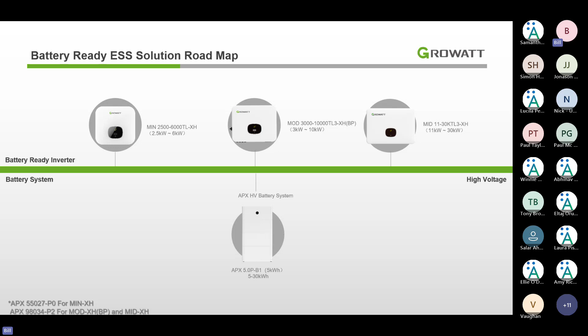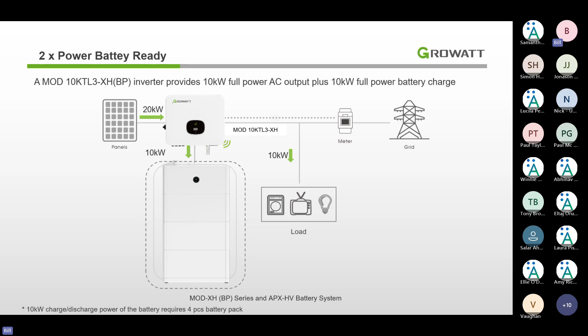Here's an example for the MOD system. So imagine this product goes up to 10 kilowatt. This system will allow like 20 kilowatt from your panels, and it will separate like 10 kilowatt to charge your batteries, and the other 10 kilowatt will feed your loads. Remember here, since this battery is 0.5 C, that means a 5 kilowatt hour battery will only have 2.5 kilowatt charge and discharge power. So when you apply this battery on the 10 kilowatt system, 10 kilowatt inverters, you will need at least 20 kilowatt hour battery that would allow you to reach the 10 kilowatt charge and discharge power of this system. So that means like 4 batteries in total, at least.